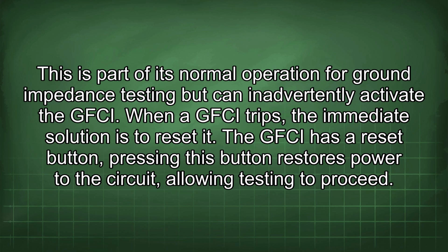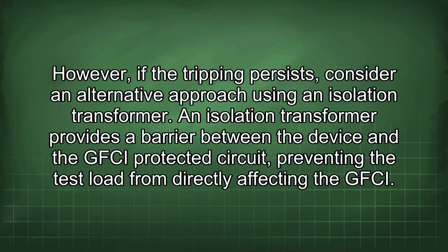When a GFCI trips, the immediate solution is to reset it. The GFCI has a reset button. Pressing this button restores power to the circuit, allowing testing to proceed. However, if the tripping persists, consider an alternative approach using an isolation transformer.